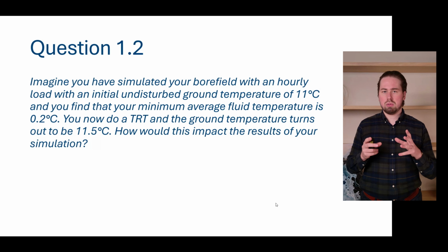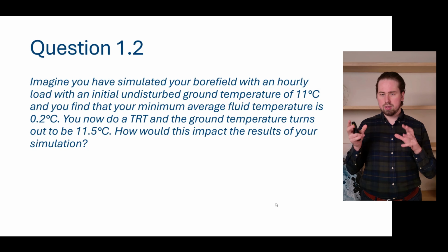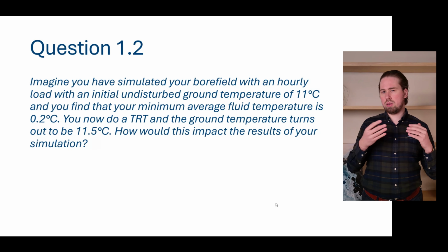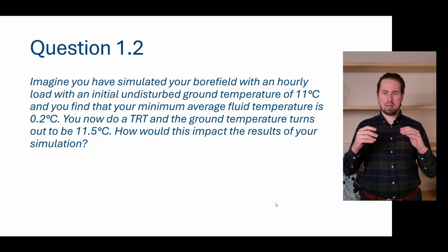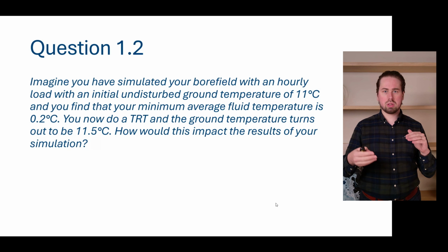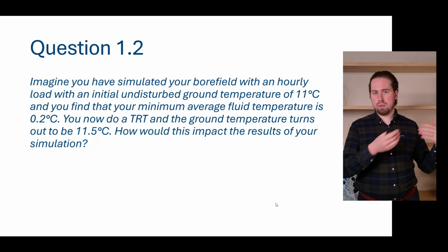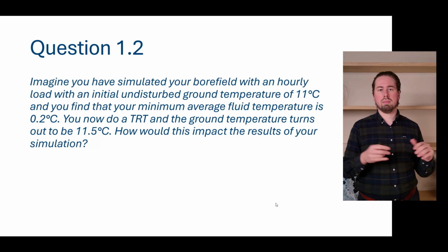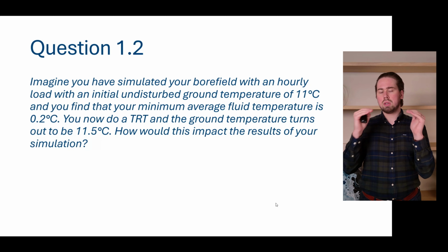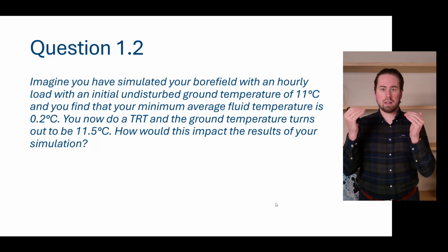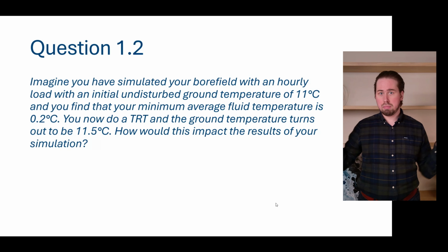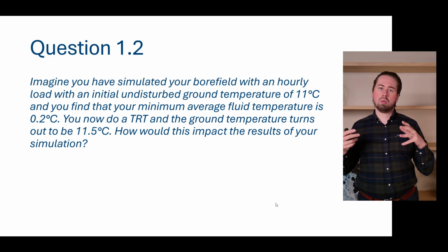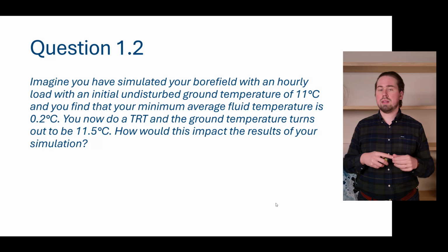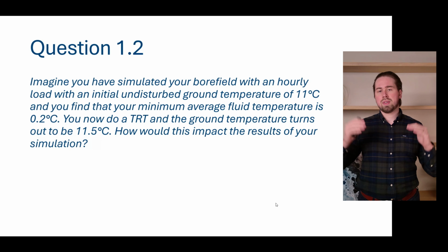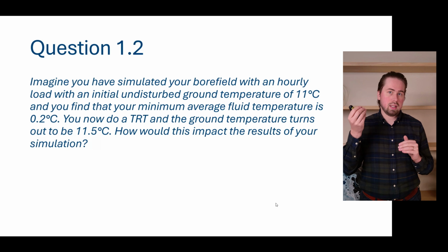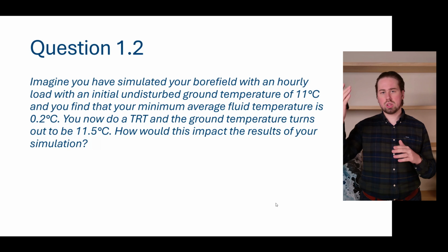If you try to answer this question, you need to distinguish between your fluid temperatures and your borehole wall temperature. We have a borehole wall temperature, which is used with the effective borehole thermal resistance to calculate the fluid temperature. But since our borehole wall temperature is now 0.5 degrees Celsius higher, our fluid temperatures will also be 0.5 degrees Celsius higher. So we won't have 0.2 degrees Celsius in the end, but 0.7 degrees Celsius, since it's all related to the initial ground temperature. And when that changes, all the other lines change as well.